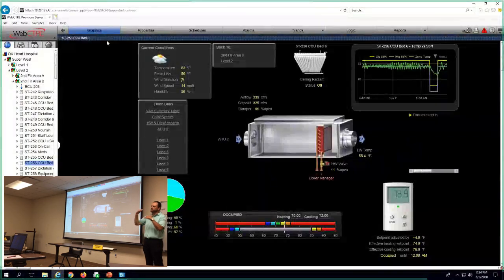There's a limited range at which we're allowing them to change that up and down. I'll show you where all those range adjustments are. That range is set at 0. Now they can adjust it up 4 or down 4 from whatever that base is. If it's 70 degrees, then that's 0, and you can go plus 4 or minus 4 from 70.